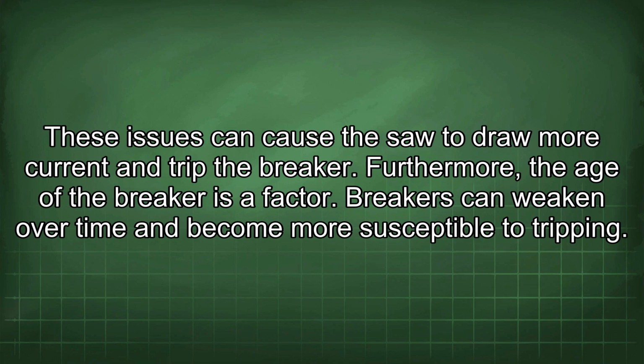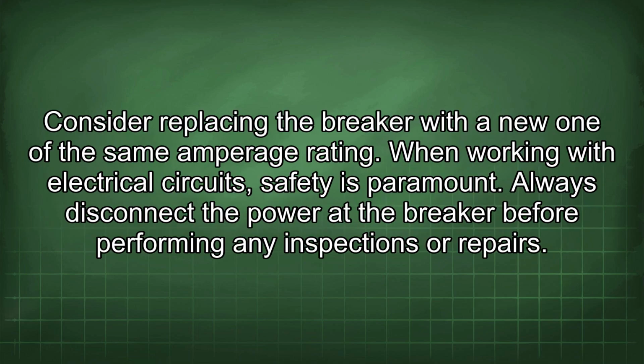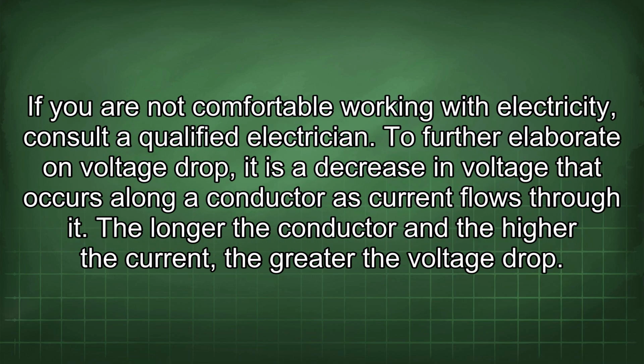Furthermore, the age of the breaker is a factor. Breakers can weaken over time and become more susceptible to tripping. Consider replacing the breaker with a new one of the same amperage rating. When working with electrical circuits, safety is paramount. Always disconnect the power at the breaker before performing any inspections or repairs. If you are not comfortable working with electricity, consult a qualified electrician. To further elaborate on voltage drop, it is a decrease in voltage that occurs along a conductor as current flows through it.